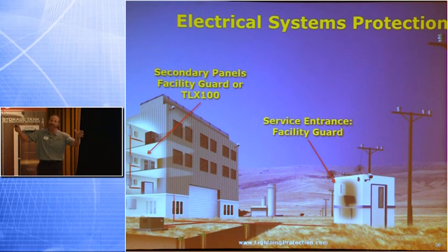So when you look at a facility, we want to look at a lightning protection approach as having 3 legs of a stool. A lightning protection system should have 3 legs of a stool as far as its protection components. Direct strike, 1 leg. Dissipation array, spline ball ionizers, provide that direct strike protection. Secondly, surge protection. I like to call it strategic surge protection. Any vulnerable power line that enters that facility should have strategic surge protection.